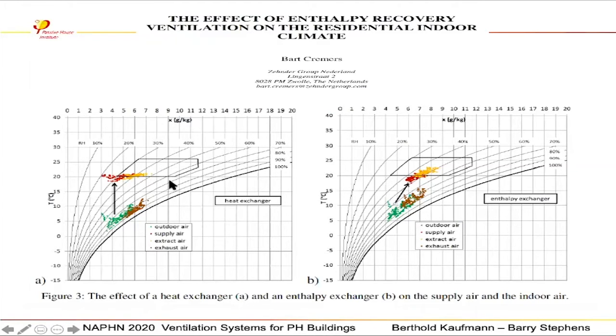What this really demonstrates is that the red dots here are supply air temperature and humidity. The yellow is exhaust air. The brown is exhaust outside, and this is the outside air in green. So what you're seeing is that the red dots, the supply air temperature, are very close to this 20 C or 68 degrees Fahrenheit. So the sensible effectiveness is very high with the HRV, but these red dots are getting a little bit outside of our humidity box here.